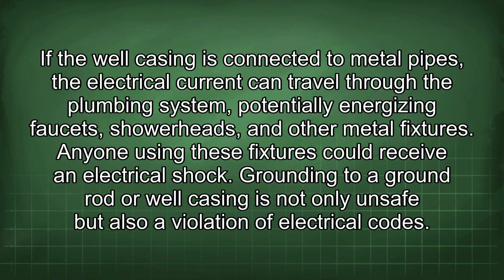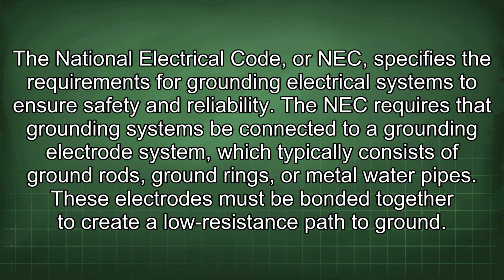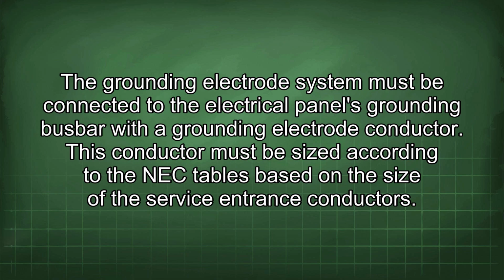Grounding to a ground rod or well casing is not only unsafe but also a violation of electrical codes. The National Electrical Code, or NEC, specifies the requirements for grounding electrical systems to ensure safety and reliability. The NEC requires that grounding systems be connected to a grounding electrode system, which typically consists of ground rods, ground rings, or metal water pipes. These electrodes must be bonded together to create a low-resistance path to ground. The grounding electrode system must be connected to the electrical panel's grounding busbar with a grounding electrode conductor. This conductor must be sized according to the NEC tables based on the size of the service entrance conductors.